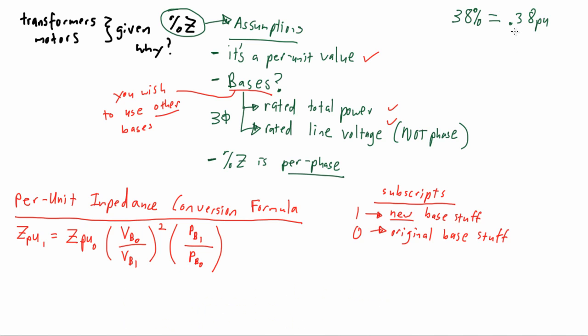So let's see this formula in action with some real numbers given. We'll use what we set up here as the 38% impedance value in our formula. Let's set up the voltage and the power bases. So let's say our original voltage base will be 480V, and our original power base will be 3 KVA.